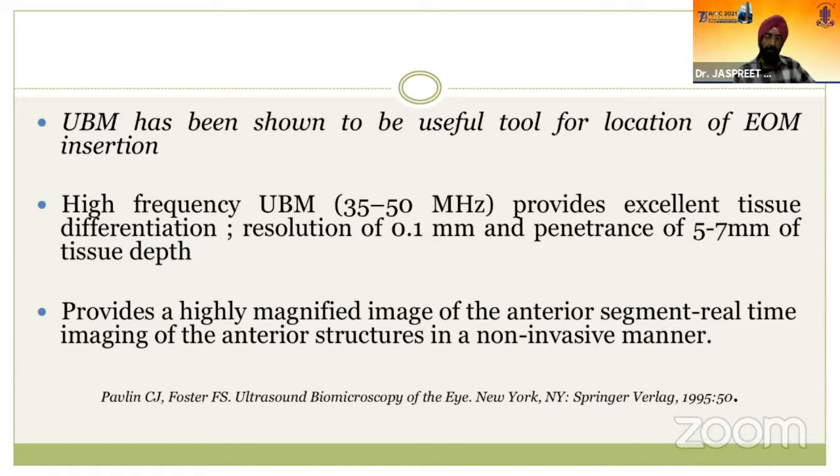It's basically a 35 to 50 megahertz probe. We have a 10 megahertz probe as well. It has excellent tissue differentiation, resolution of 0.1 millimeter, and a good penetrance. It provides a magnified image of the anterior segment, which is real time, in a non-invasive manner.